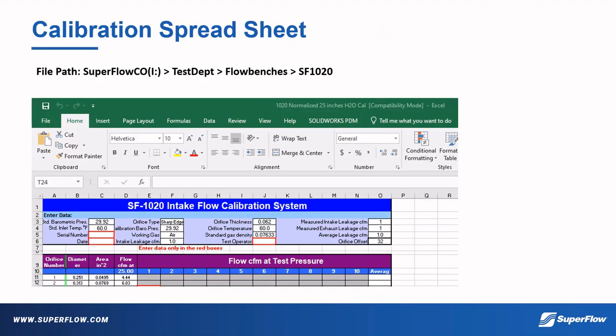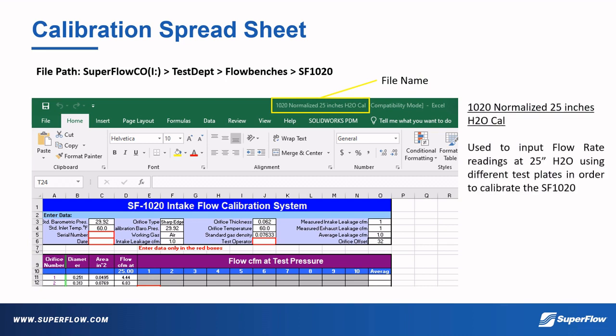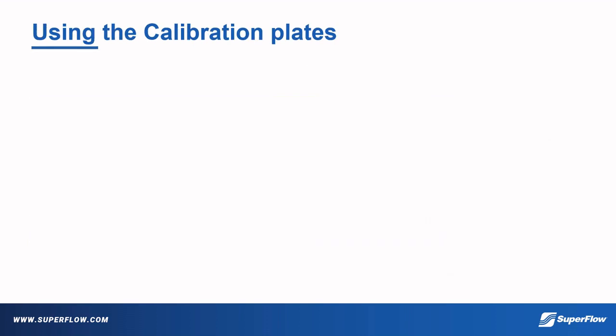In order to get accurate calibration data, you'll need to use this Excel document with a laptop while testing. The document can be found under SuperFlow Colorado's I drive, Test Department, Flowbenches, and then in SF-1020. The file name is 1020 normalized 25 inches H2O cal. This document is used to input flow rate readings at 25 inches H2O pressure using different test plates and different orifices to calibrate the SF-1020.